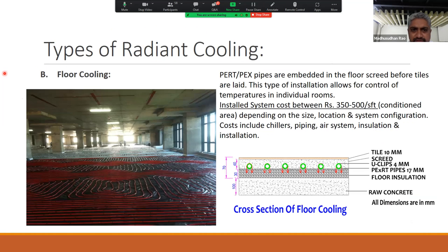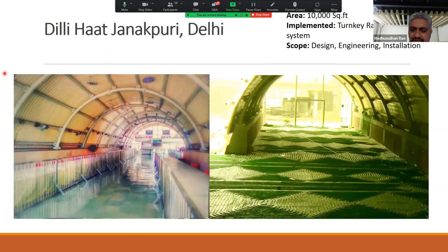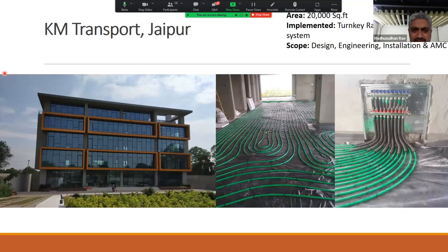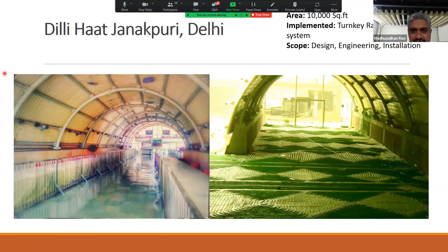I'll just skip ahead and show you what has been used in different projects. This is a project in Jaipur, where radiant heating as well as cooling is there. It's primarily floor-based cooling or heating, aided by relatively smaller size. An AHU was not used. So fan coil units were used for the fresh air as well as the balance sensible cooling.